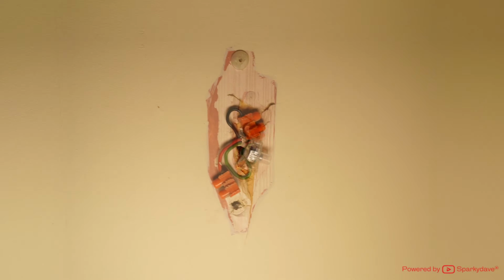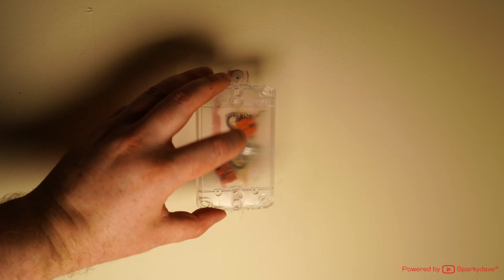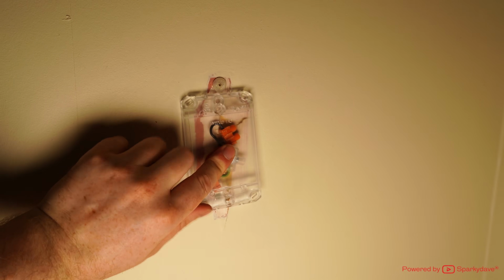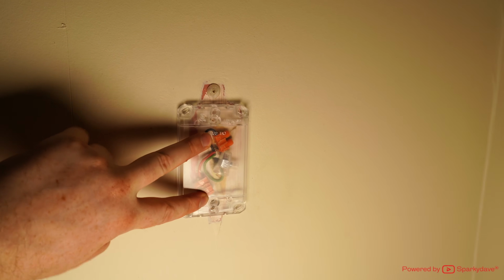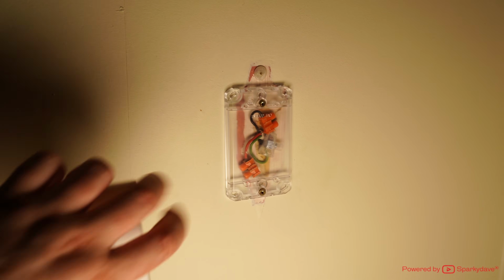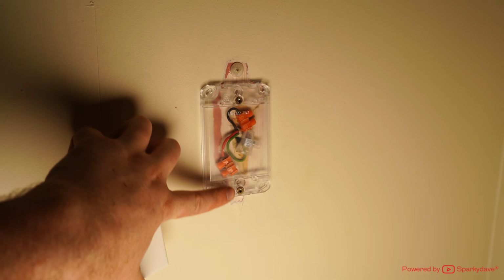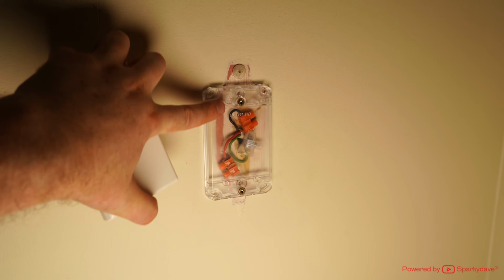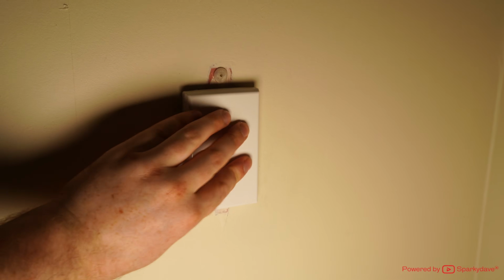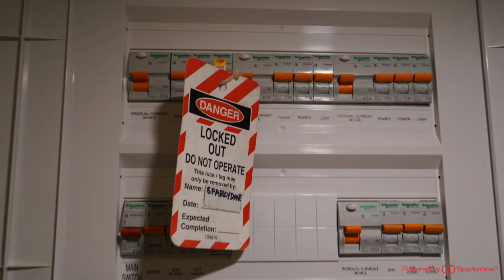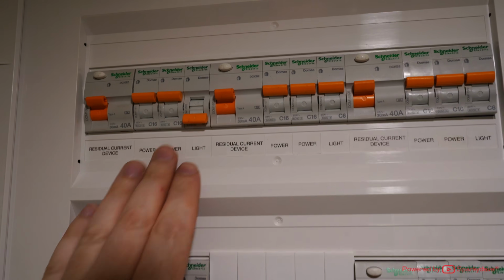Install connectors onto the free cable ends where the wall light will be reinstalled later, and cover them with a blank plate temporarily. Ensure to screw the blank plate into the wall where the wall light can cover the holes when reinstalled. Once covered, safely remove the lockout and tag from the switchboard.